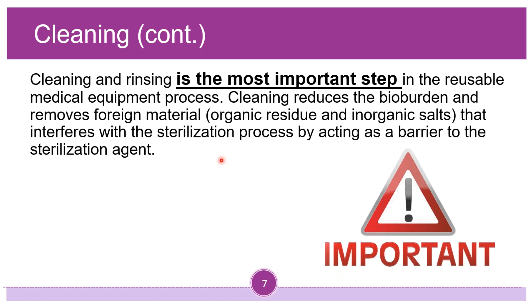Decontamination. Reusable items should be transported from the point of use to the reprocessing area in closable, puncture-resistant, leak-proof containers that are properly marked as biohazard. Standard precautions should always be adhered to when handling contaminated medical equipment. Contaminated items should be transported to a decontamination area where they must be thoroughly cleaned and decontaminated using water with detergents or enzymatic cleaners. Quick polling question.